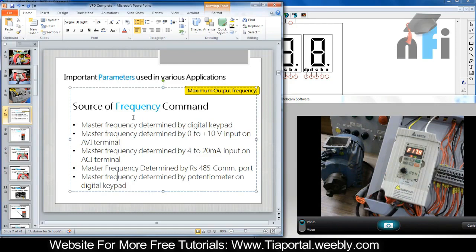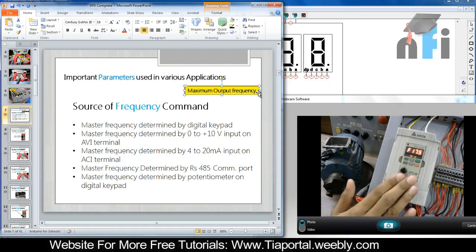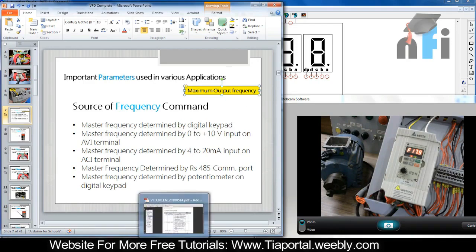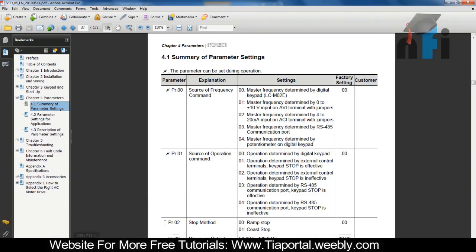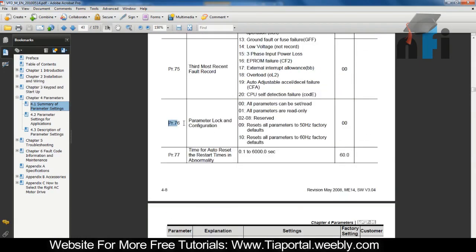Before setting this parameter, we need to mention the maximum output frequency in your drive. Many times you don't know what parameters are already fed into your VFD. The first step a programmer should do before entering parameters is to reset all parameters already in the drive, so you're aware of what you are entering. You should always carry the manual of your drive. In this manual, the reset parameter is number 76. Entering 09 in parameter 76 resets all parameters to 50 Hz factory defaults.